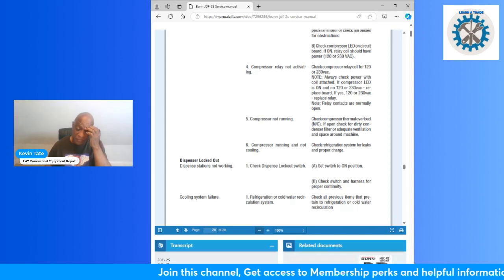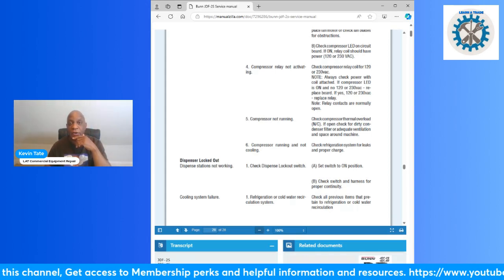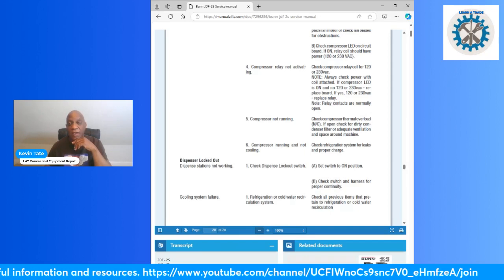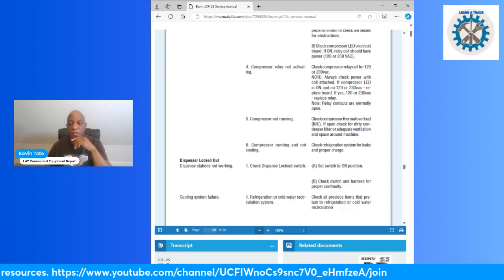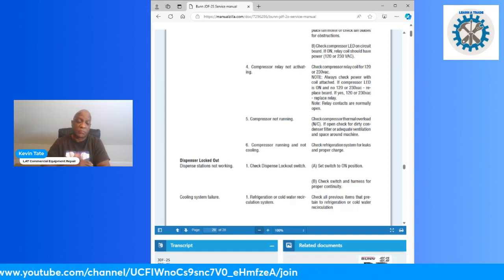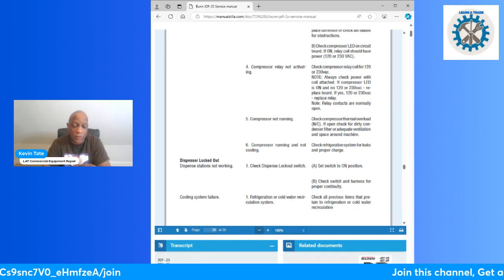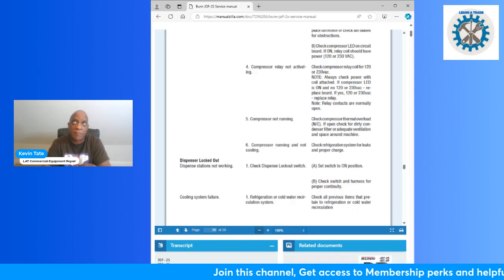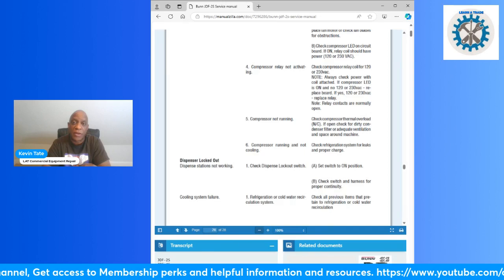Another cause could be a compressor running and not cooling. So it could be low on refrigerant, possibly a refrigerant leak. Another thing that I found too was the water bath not being up to the proper water level, the water level not being set right.